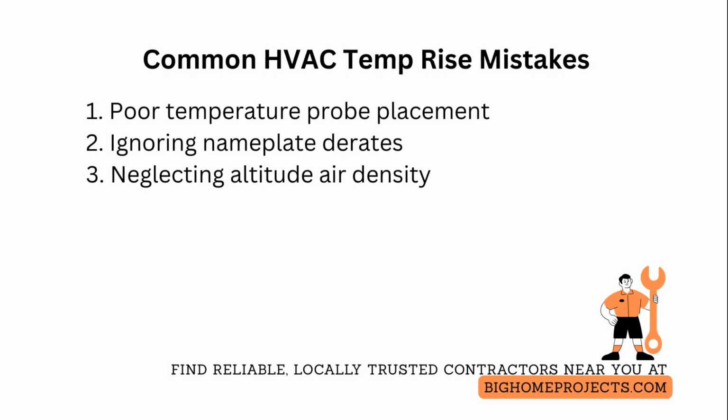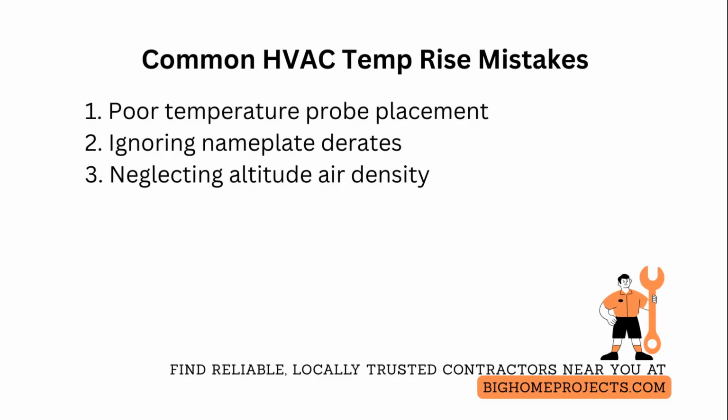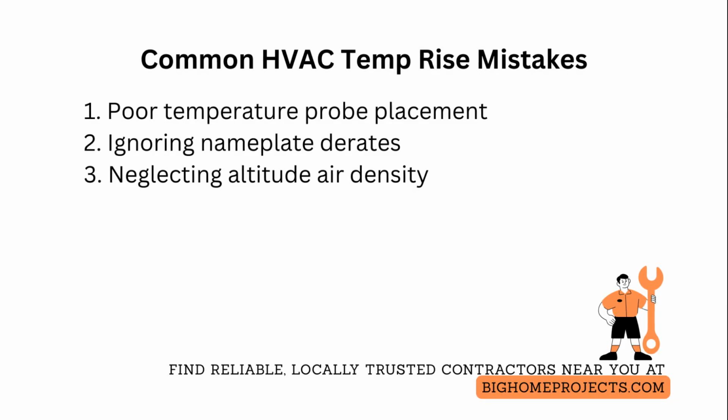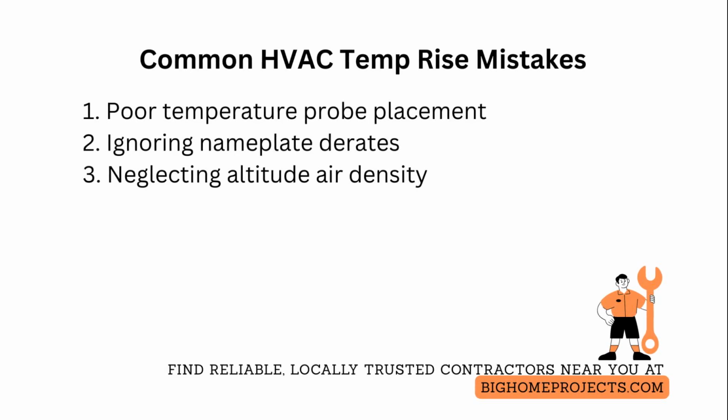Second common issue is using nameplate BTU without accounting for derates or installation losses, leading to overestimated airflow. Fix by reviewing the furnace installation manual and applying the correct derate factors or measuring input and output power where applicable.